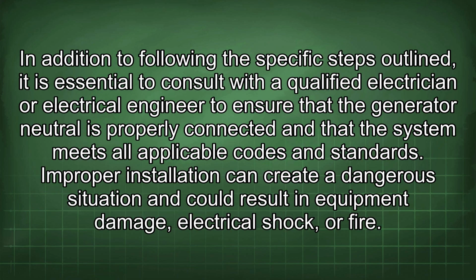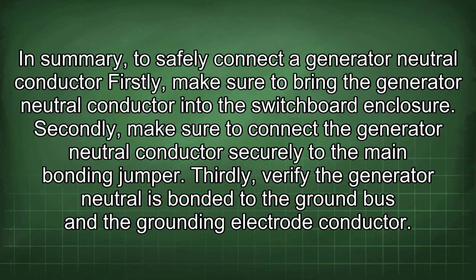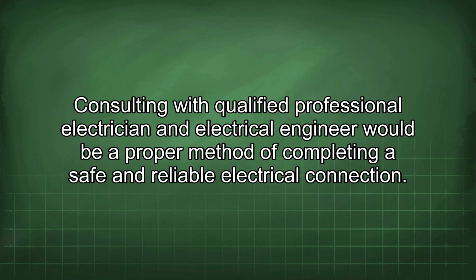In addition to following the specific steps outlined, it is essential to consult with a qualified electrician or electrical engineer to ensure that the generator neutral is properly connected and that the system meets all applicable codes and standards. Improper installation can create a dangerous situation and could result in equipment damage, electrical shock, or fire. In summary, to safely connect a generator neutral conductor, firstly, make sure to bring the generator neutral conductor into the switchboard enclosure. Secondly, make sure to connect the generator neutral conductor securely to the main bonding jumper. Thirdly, verify that the generator neutral is bonded to the ground bus and the grounding electrode conductor. Consulting with a qualified professional electrician and electrical engineer would be a proper method of completing a safe and reliable electrical connection.